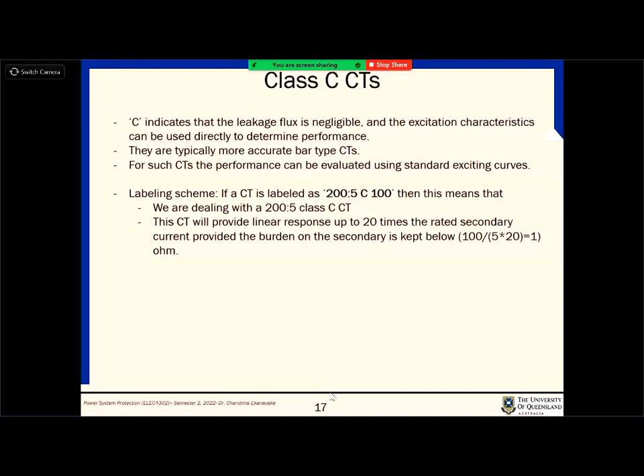So when you are dealing with the real world, if you go into the industry, you will find that CTs are labeled as shown here, 200 to 5 C100. When you see this, it gives you a lot of information, right? The primary current is 200 amps, the secondary standard current is 5 amps, the class is C, the ratio between the primary and the secondary is 200 to 5, and the CT will provide linear response up to 20 times the rated secondary current, provided the burden on the secondary is kept below 100 divided by 5 times 20, which is equal to 1 ohm in this case.